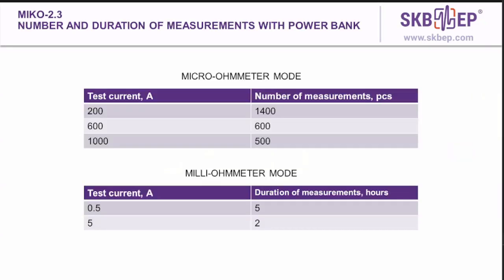Here on this slide, there is a table with the number and duration of the measurements with the use of the power bank for the most required modes of micro-ohmmeter and milliohmmeter. According to the table, we can see that we don't really need to connect the instrument to the mains. So the power bank is quite sufficient for that.